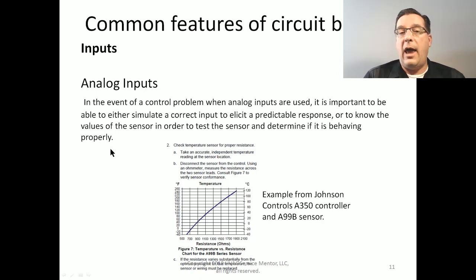In the event that you have an analog input, typically a temperature or pressure sensor, it is important to be able to either simulate a correct input to elicit a predictable response, or to know the values of the sensor in order to test that sensor and determine if it is behaving properly. So say, for example, you have something that is not controlling to the right temperature and is using a temperature sensor. You need to know how that sensor is supposed to work, which means you're going to have to do some research. It's not going to be printed anywhere on the equipment or anywhere on the sensor. It may be in the IOM, or it may be in some other specification that you're going to have to hunt for. You may have to call up tech support to get it. And this is for a thermistor.